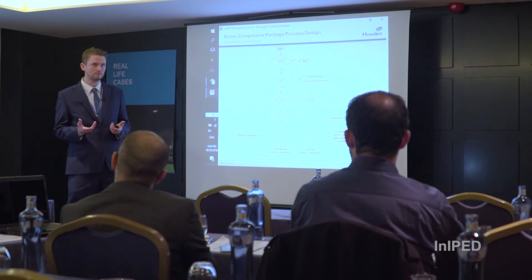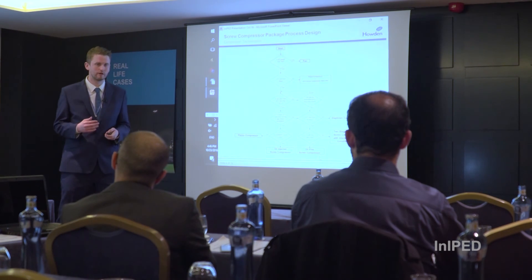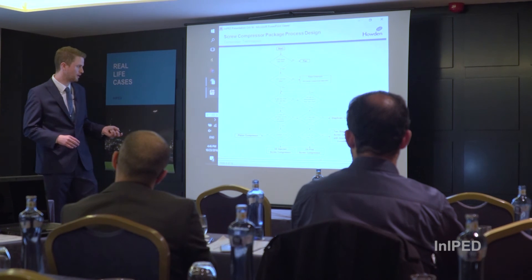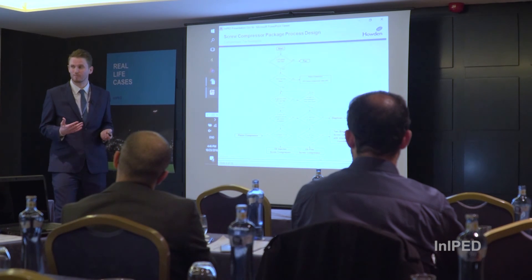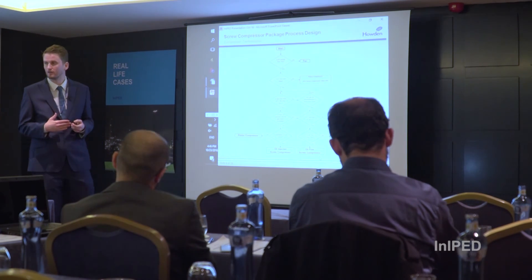A lot of the applications we work on, we work in competition with piston compressors — even Howden also provide piston compressors. But the key benefit of the screw compressor is that because of the rotating movement of the compressor, instead of a forward and backwards motion, you don't get the same wear that you would on a piston compressor. So the availability and reliability of screw compressors is higher than a piston compressor.